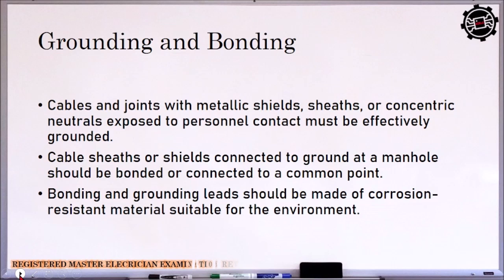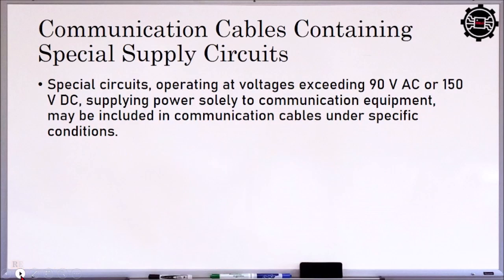Then communication cables containing special supply circuits. So special circuits operating at voltage exceeding 90 volts AC or 150 V DC, supplying solely for the communication equipment, may be included in communication cable under specified conditions. So meaning ito yung mga supply circuit for our communication equipment. Katulad ng mga telephone na kailangan silang mayroong sariling DC voltage, or sa fiber box kailangan may sariling DC voltage. So pwede na yung kanyang supply cable is isama na doon sa ating communication cable, with the specific conditions. So ano yung mga conditions na ito?